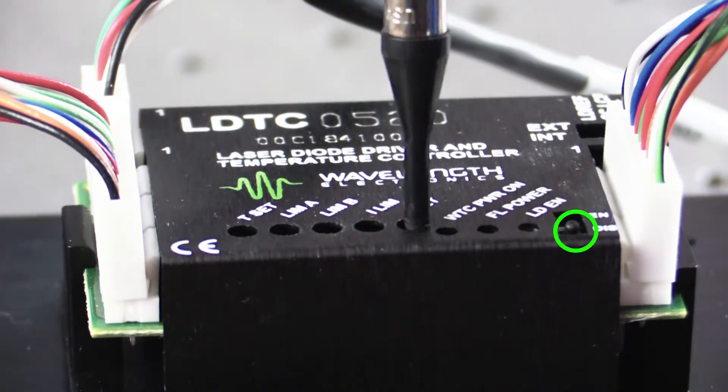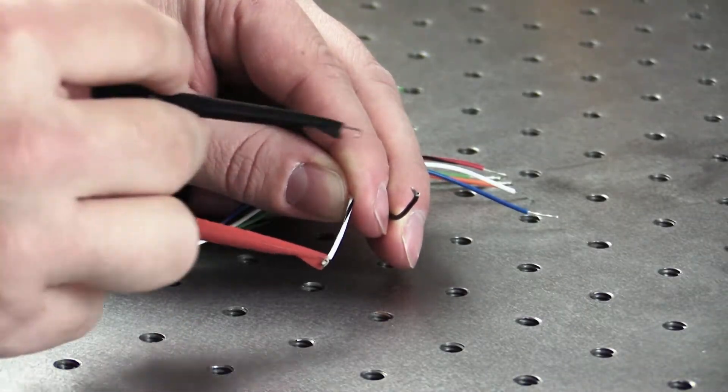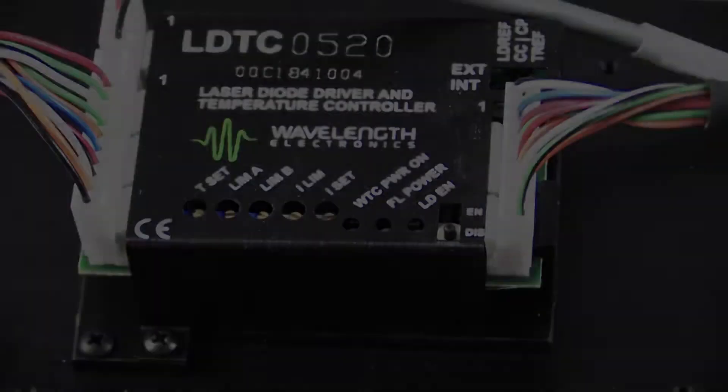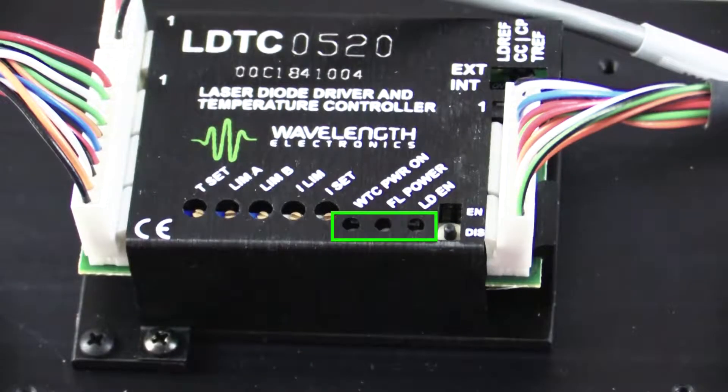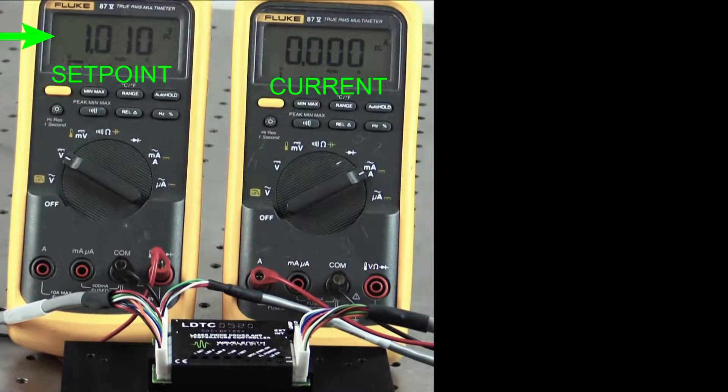Also ensure the LD enable switch is disabled. To monitor the temperature set point, connect the voltmeter to SET Tmon and common. Switch on the power supply. The WTC power on LED and FL power LED will illuminate green. As soon as power is applied, the temperature controller is active.